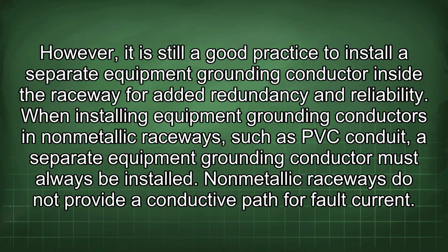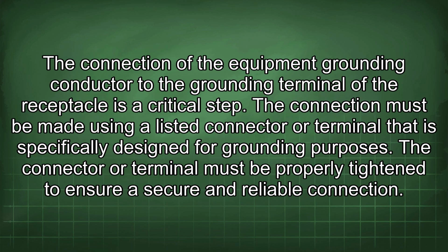However, it is still a good practice to install a separate equipment grounding conductor inside the raceway for added redundancy and reliability. When installing equipment grounding conductors in non-metallic raceways, such as PVC conduit, a separate equipment grounding conductor must always be installed. Non-metallic raceways do not provide a conductive path for fault current. The connection of the equipment grounding conductor to the grounding terminal of the receptacle is a critical step. The connection must be made using a listed connector or terminal that is specifically designed for grounding purposes. The connector or terminal must be properly tightened to ensure a secure and reliable connection.